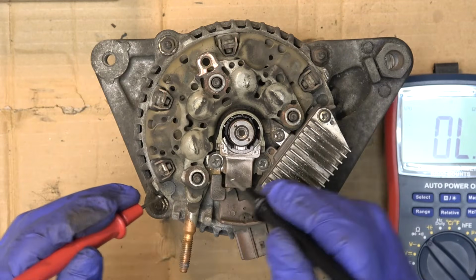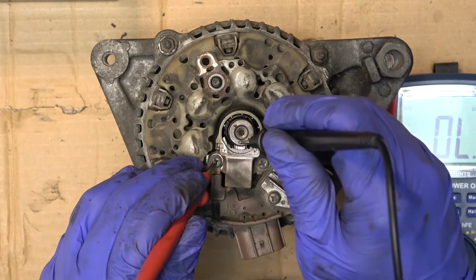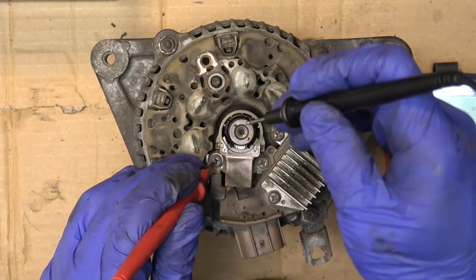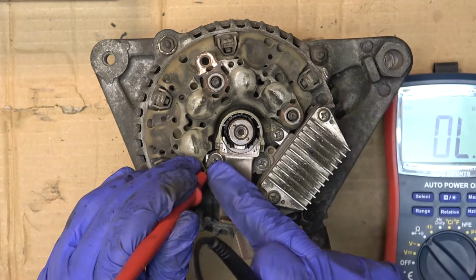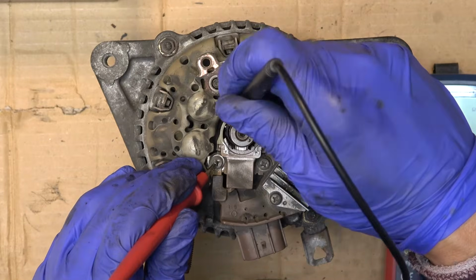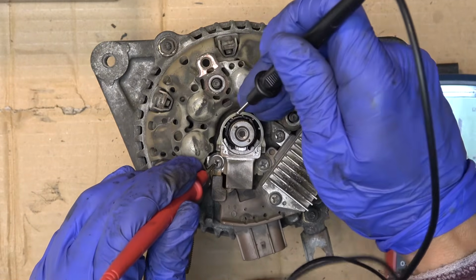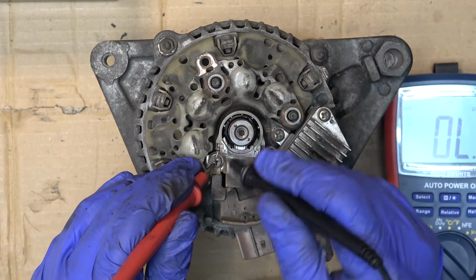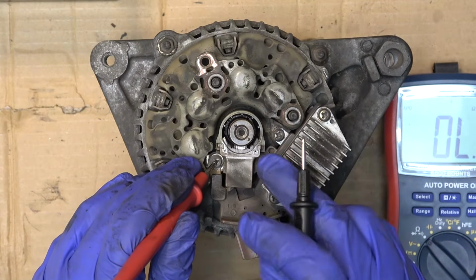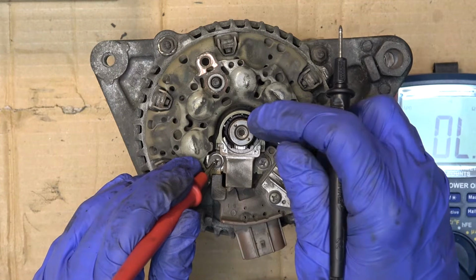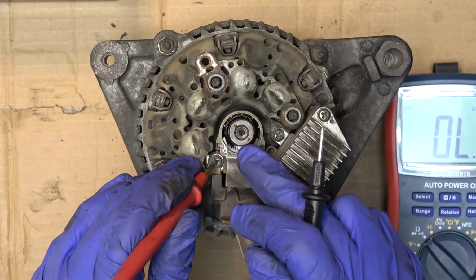Let me try on this side here. So on this side, it should be the bottom brush. I measure from this point here to the bottom slip ring. You see it beeps, that means it's continuous. So the brush is touching the slip ring on the bottom, but not the slip ring on the top.